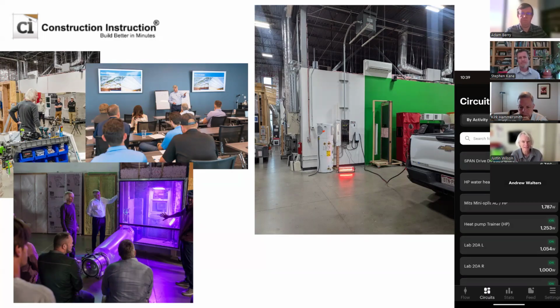So it's breaker space, and that's why I saw with Kirk two panels, because it wasn't about the ampacity the house required. It was about the fact that we add car charging, we add backup heat, we add this. There's a heat pump water heater, and so it's not necessarily about the load on the house. It's that I need 40 or more breaker spaces in a typical panel to have, was sort of my note, breaker capacity more than electrical capacity of the building, because there's so many different things that may or may not run at any given time.